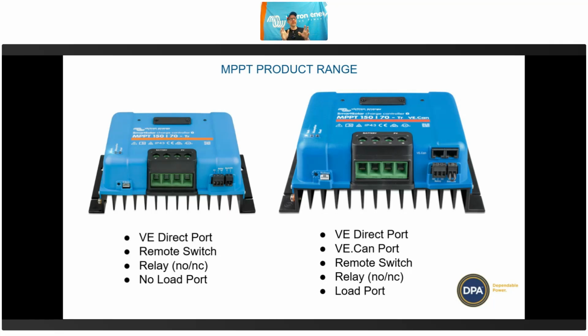Within reason, you're not going to damage the MPPT by putting a larger array on it than that calculation I showed you. You can put as large an array on as you like within reason, and it can just throttle it off if it doesn't have any use for it. It can just make its resistance high, and then there'll be no current and no power. But if you put too much voltage into it, then you will break it, because the components have a set voltage range. There's a calculator on the Victron website, which will help you work out your string voltages and what size MPPT to use as well.